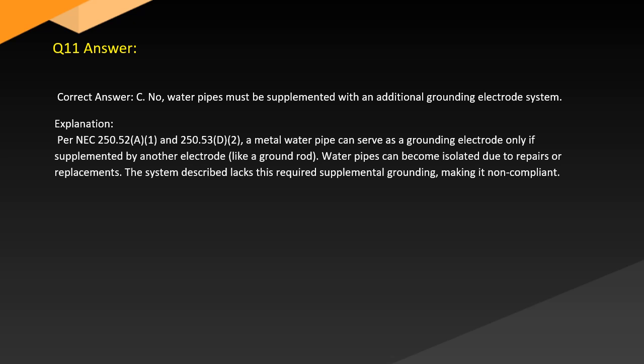Answer. Correct answer: C. No, water pipes must be supplemented with an additional grounding electrode system. Explanation. Per NEC 250.52(A)(1) and 250.53(D)(2), a metal water pipe can serve as a grounding electrode only if supplemented by another electrode like a ground rod. Water pipes can become isolated due to repairs or replacements. The system described lacks this required grounding, making it non-compliant.